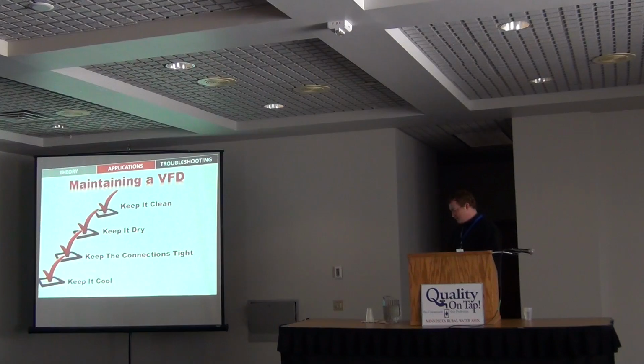So, maintaining it. Just some tips. Keep it clean, keep it dry. Check the connections and make sure they're tight. Obviously not while it's energized, but connections can come loose, and when they come loose, heat is generated. When heat is generated, products and devices fail. Thermal imaging can detect this, or routine maintenance. And then keep it cool. Make sure your fans are running. If they die, replace them. And yeah, keeping it clean. Replace the filters on the input side, and make sure your drive isn't getting dirty. It's just like your home computer or work computer too.